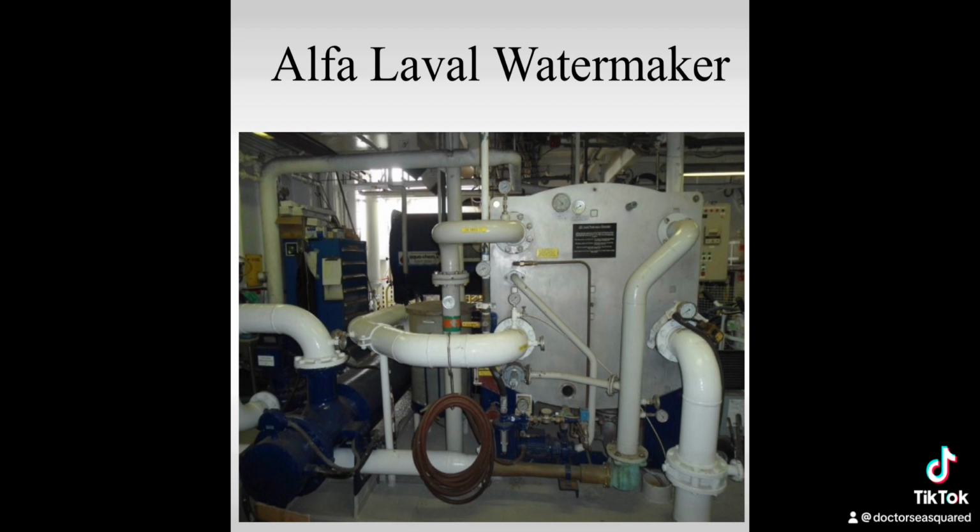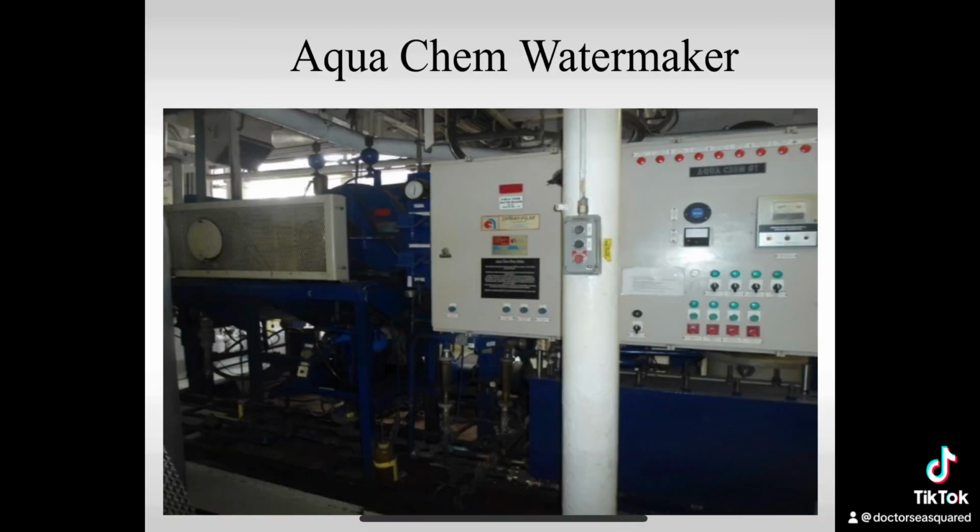So we run the water that we make through rehardening filters, which add minerals to the water and adjust the pH. From that, we filter it through a series of bag filters, UV filters to kill any bacteria, and then we dose the water with bromine, a chemical that does the same job.